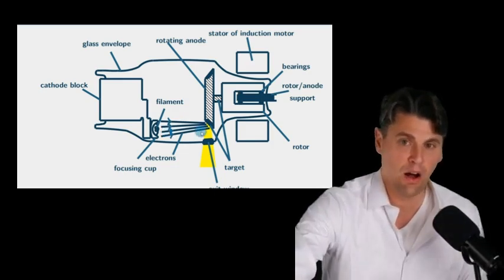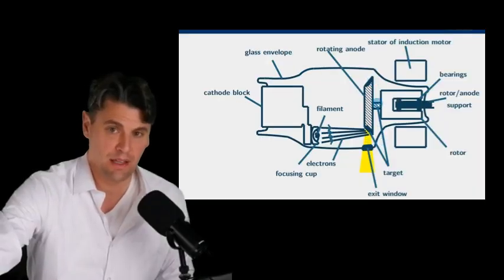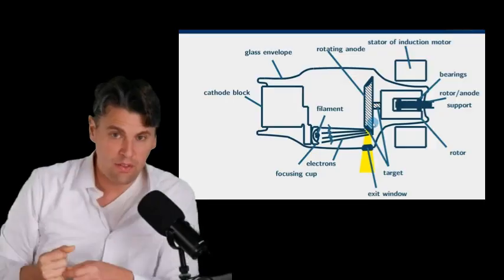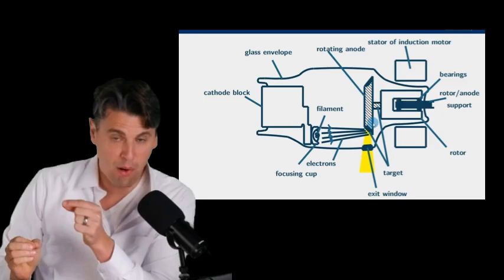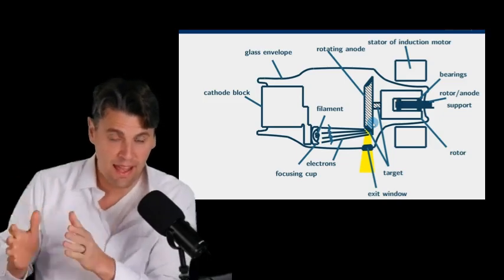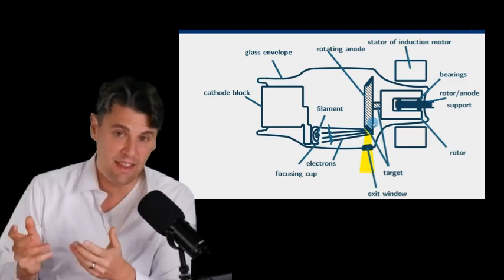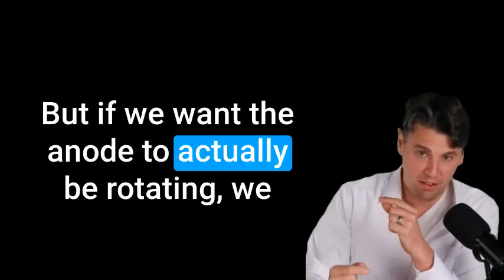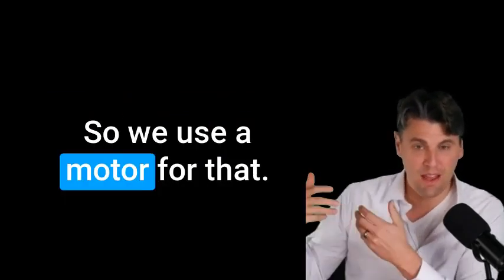On modern tubes we also have this anode. Instead of being just a stationary piece of metal, it's actually going to rotate around so that we have more ability to hit different parts on that anode so that the anode gets a chance to cool. Thus we can have a higher incident on the anode without melting the anode. But if we want the anode to actually be rotating, we need something to make that anode rotate. So we use a motor for that.